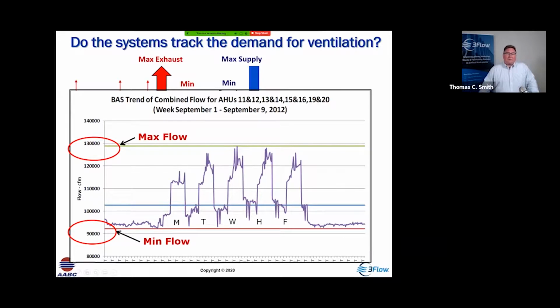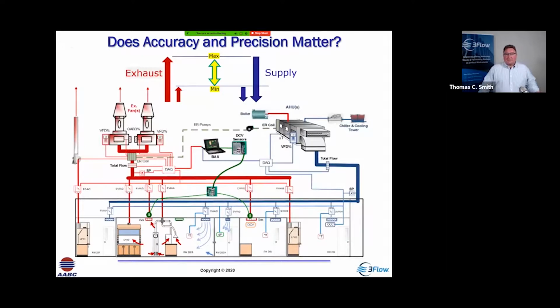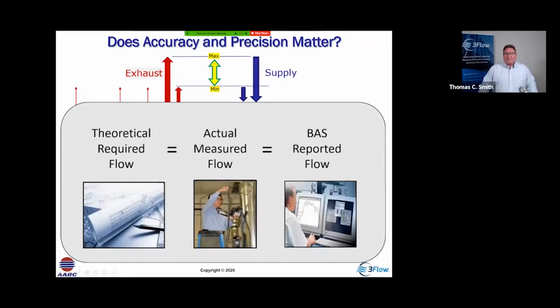How do we determine the min to max flow and what this averages over time so that we can verify that the system's operating properly within its expected operation? The accuracy and precision of the data matters. What we measure at the hoods, what we measure at the supply is critical because it's what's used to calibrate the controls. So our theoretical flow, whatever it was designed to be, should compare favorably to our actual, and that needs to then compare to the measured or reported values.